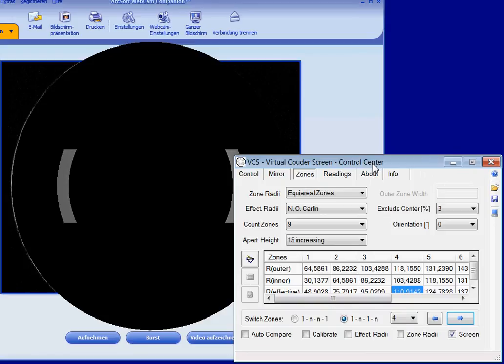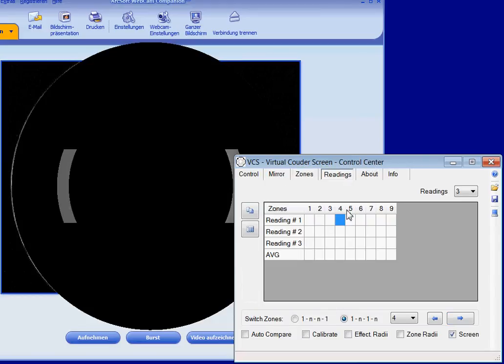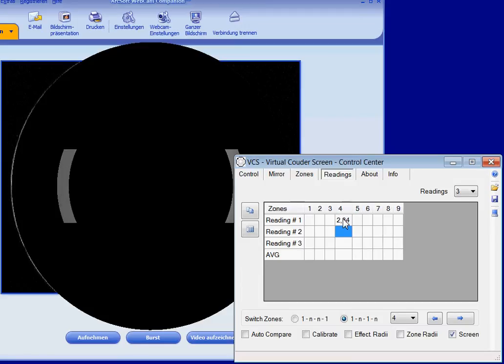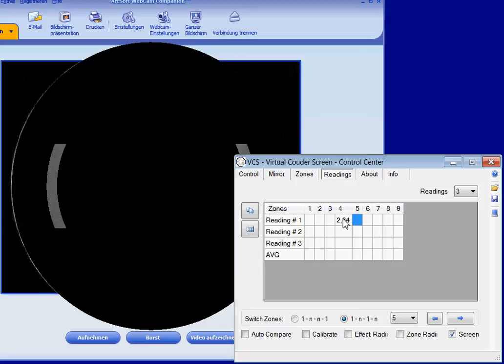As soon as I have found the center of curvature for a certain zone, I read the current position of the knife edge and write the value to the readings grid. As you see, the input field changes automatically as soon as I switch to the next zone.